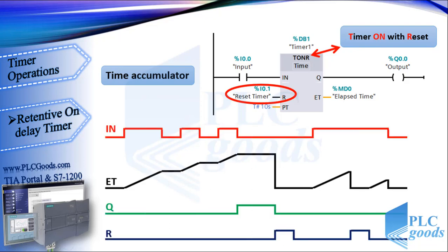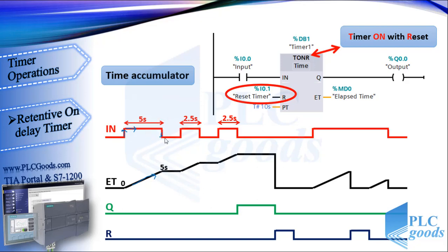Now let's see how this timer works. First, suppose there are three pulses at the IN input. When the signal state at the IN input changes from 0 to 1, the time measurement is executed. The time values are increased and accumulated when the IN input has signal state 1. For the first pulse, the ET values start from 0 to 5 seconds. When the signal state at the IN input changes from 1 to 0, the ET output holds the elapsed time, which is 5 seconds.